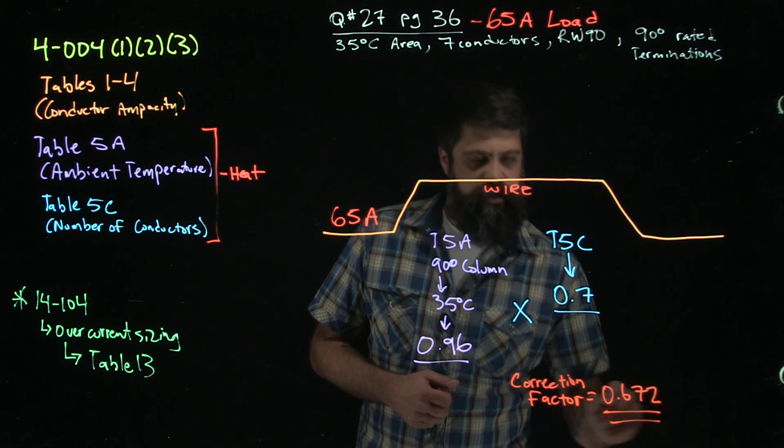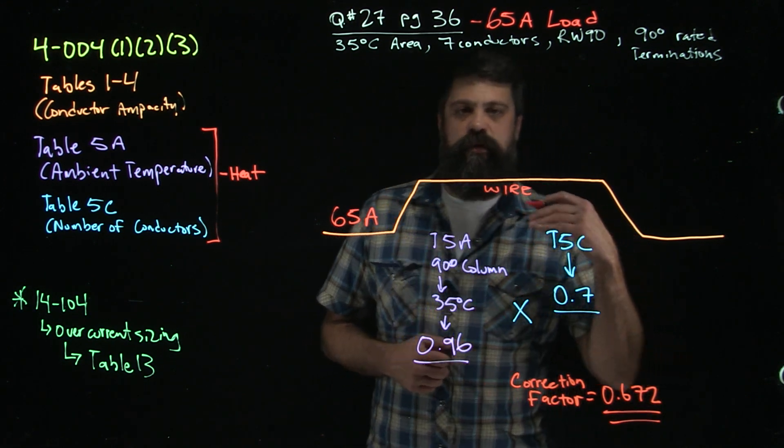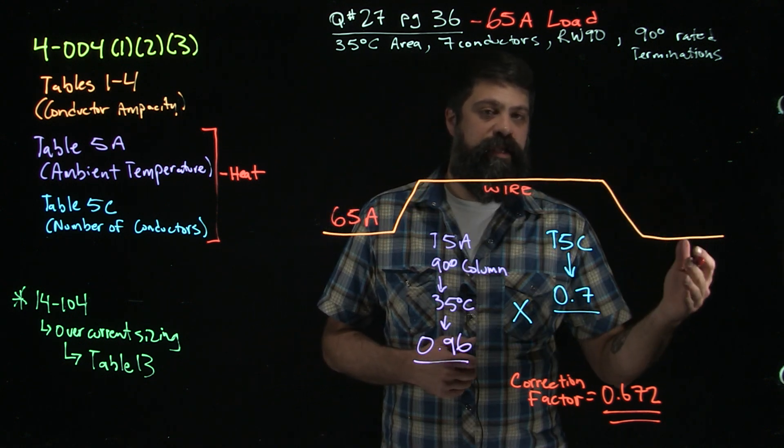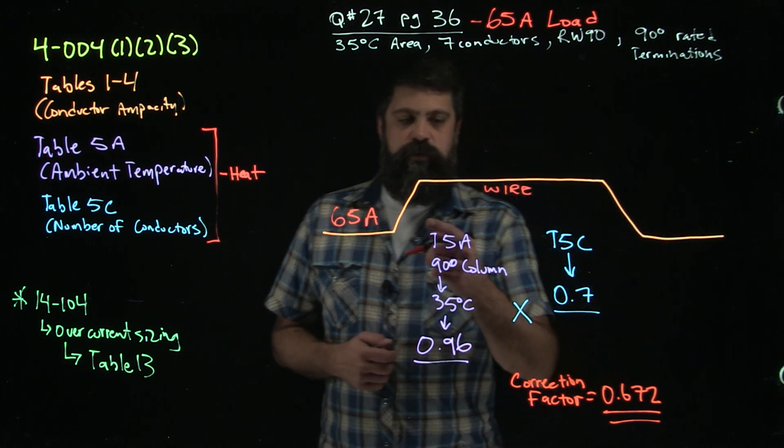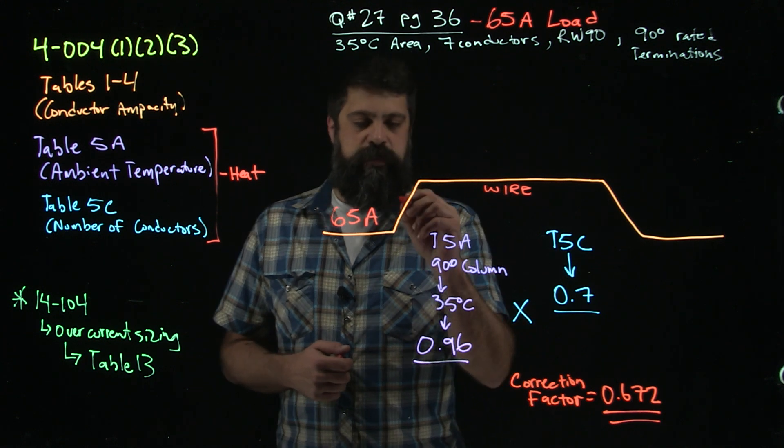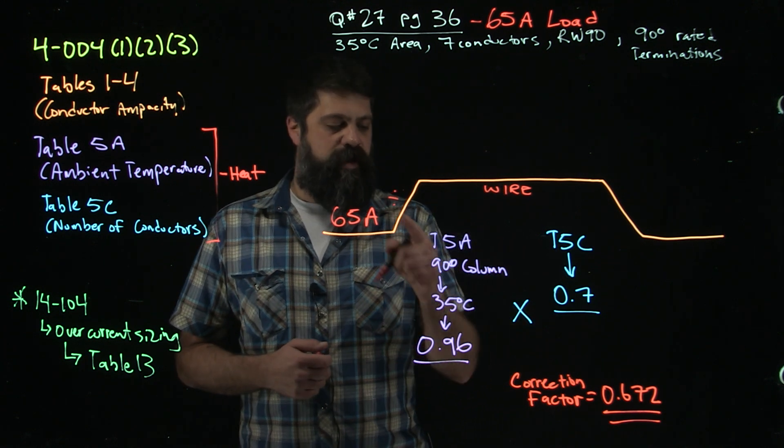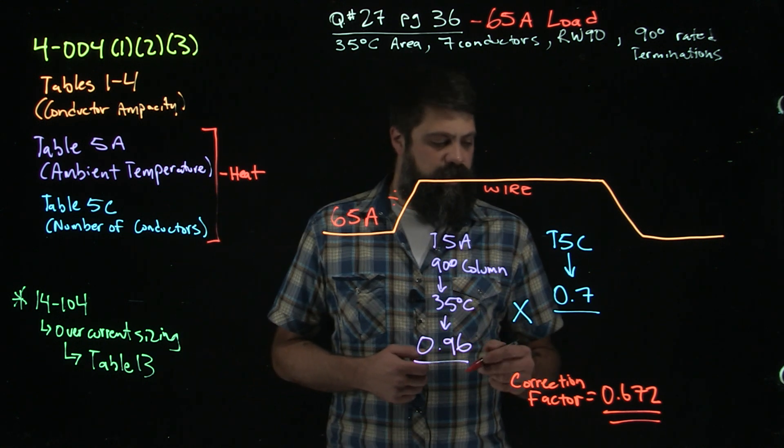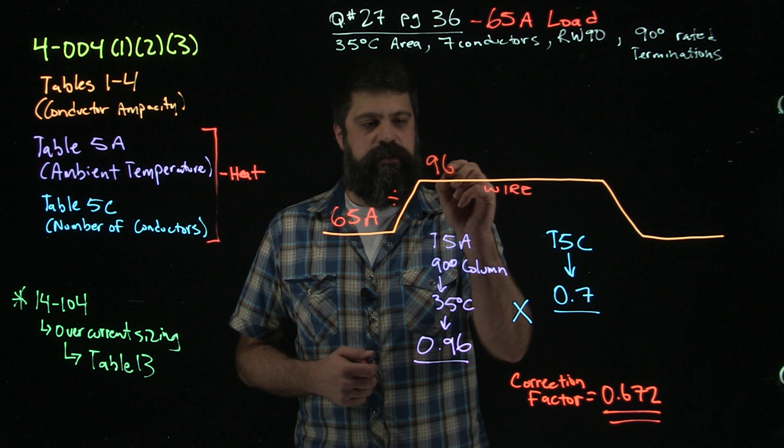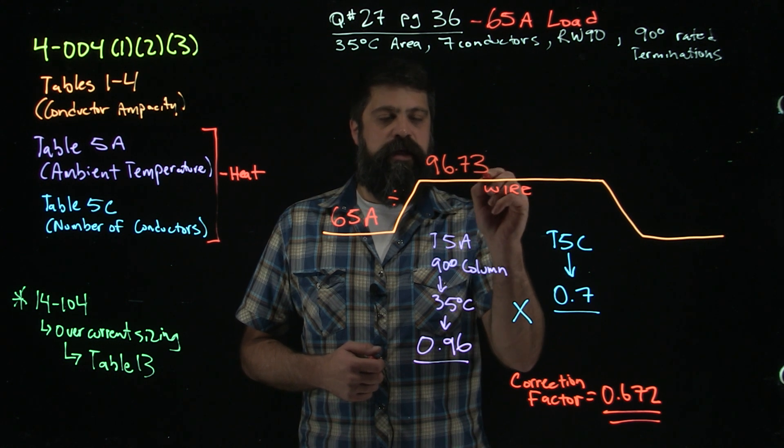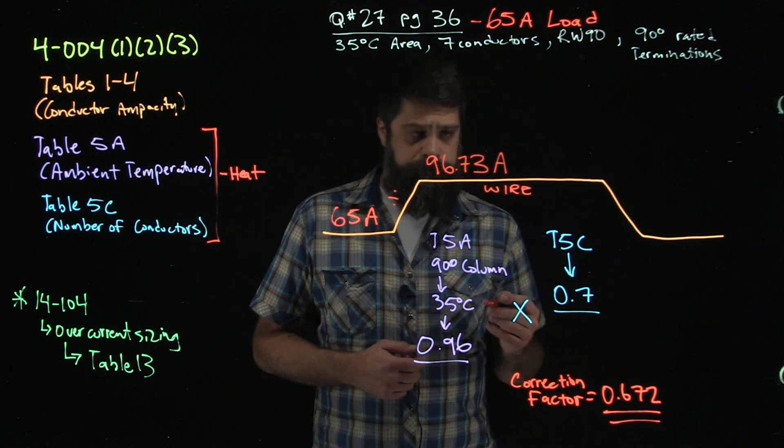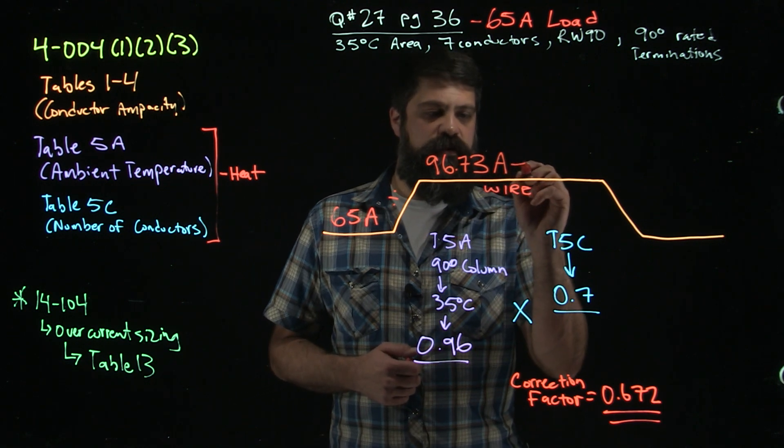This is the number that I'm going to use to figure out what is the required ampacity of this wire, and also once we find that wire, what is the allowable ampacity of that wire. So in order to find the required ampacity of this wire, I'm going to divide 65 by my correction factor of 0.672, which is going to give me a number of 96.73 amps. That's what I need this wire to be able to handle.